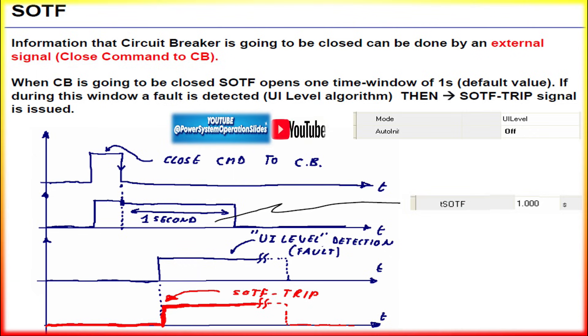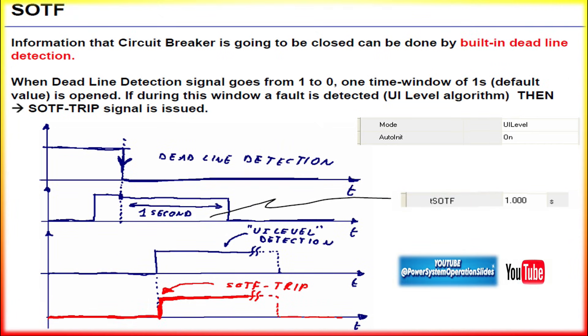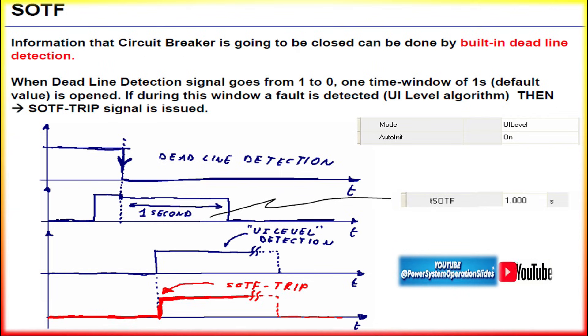As an operational example: suppose a transmission line is under maintenance and the circuit breaker is open. A fault occurs on the line — e.g., a fallen tree causing a short circuit. When maintenance is finished and the operator attempts to close the breaker, the SOTF logic recognizes that the line is still faulted. Upon breaker closure, the relay detects high fault current and low voltage immediately and sends a trip command within milliseconds to reopen the breaker, thereby protecting the system from damage.